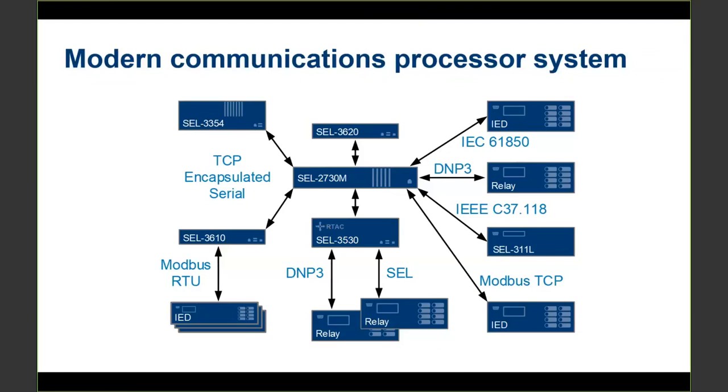And the RTAC can also communicate using many types of protocols: Modbus RTU, which is the serial one, as Scott said, Modbus Ethernet, DNP Ethernet, DNP serial, synchrophasor by serial, synchrophasor by Ethernet, and also protocols provided by the standard IEC 61850. So I can poll relays using 61850 MMS or receive GOOSE messages, IEC 61850 GOOSE messages, from the relays to my RTAC.